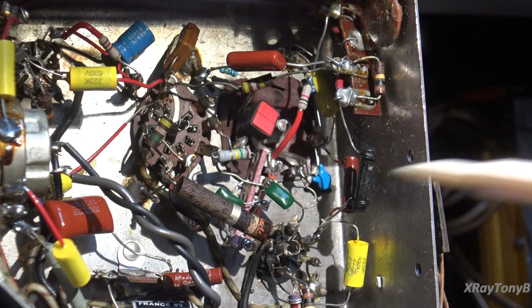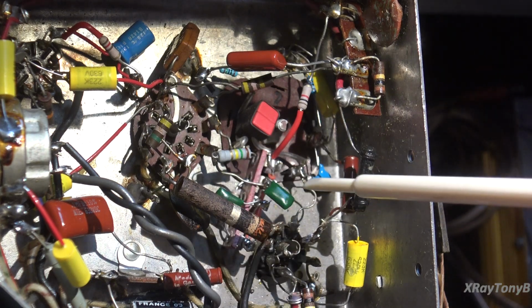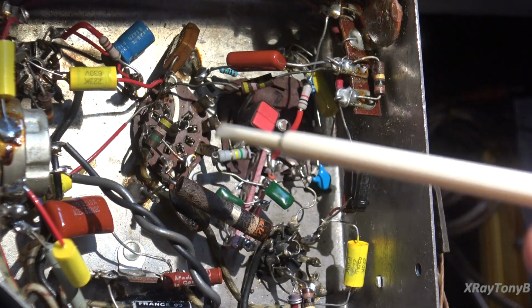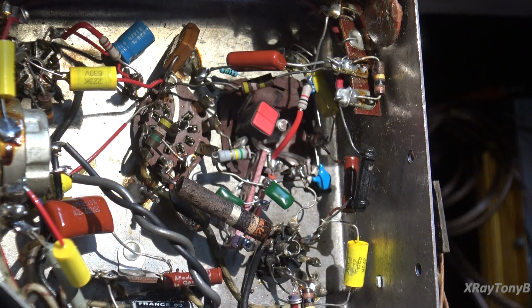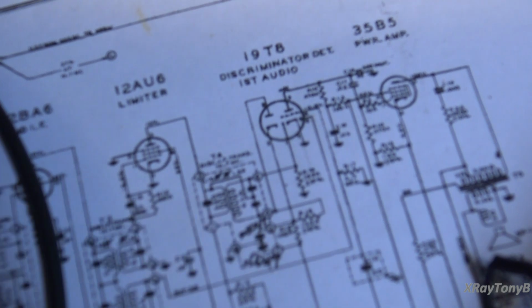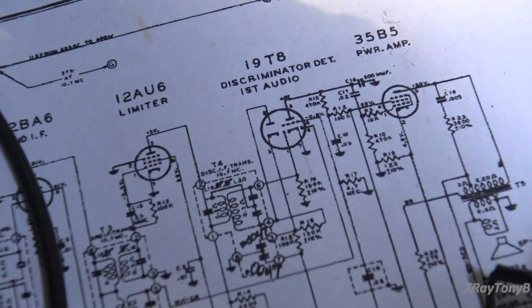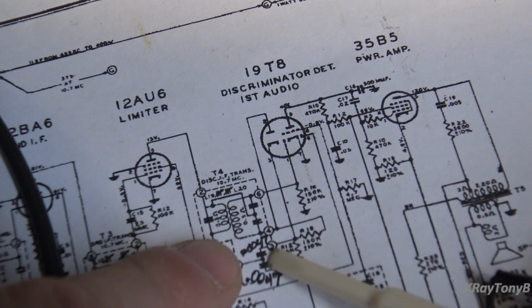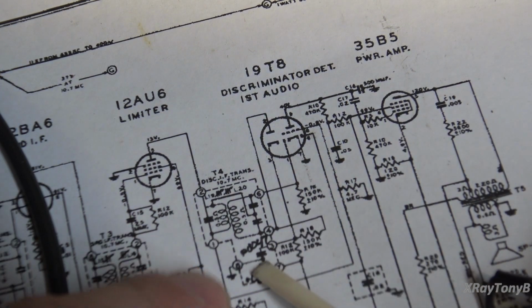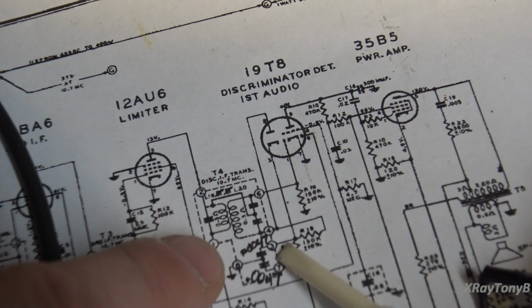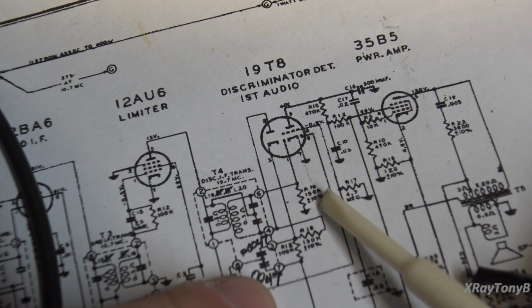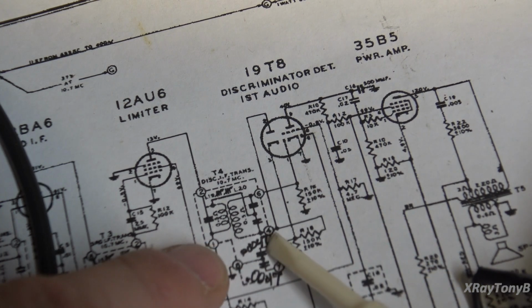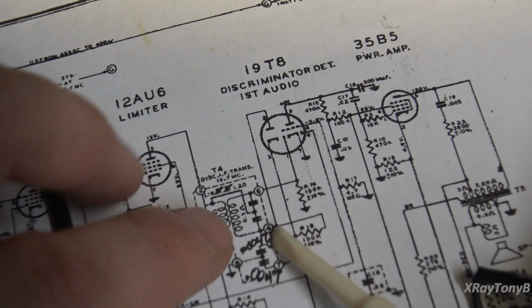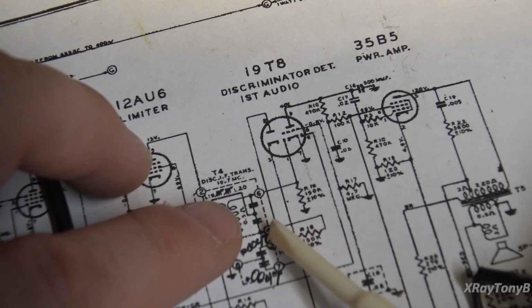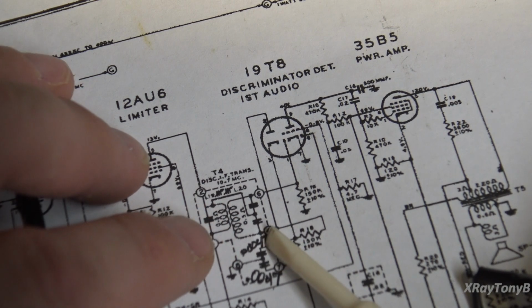What the downside is, these are very susceptible to noise. Positioning of these capacitors, if I bend them up or down a little bit, you'll actually get noise and artifacts like that in it. And what those are is these, let me focus you in, these little capacitors down here. This is where your discriminator is, and this actually takes each side of your discriminator to ground, okay, and couples it to ground through these 0.0047. I was able to measure them, and they were 0.005, both of them, and they were right on.